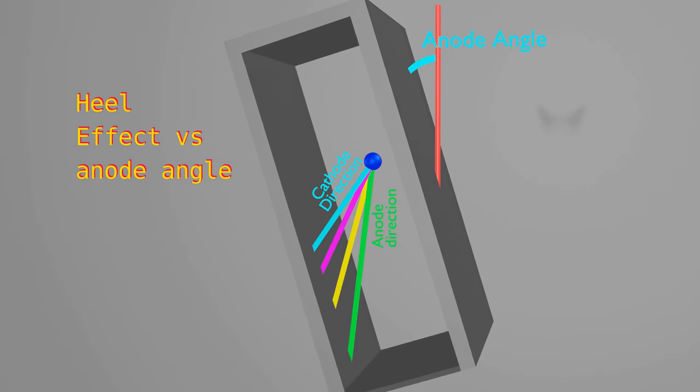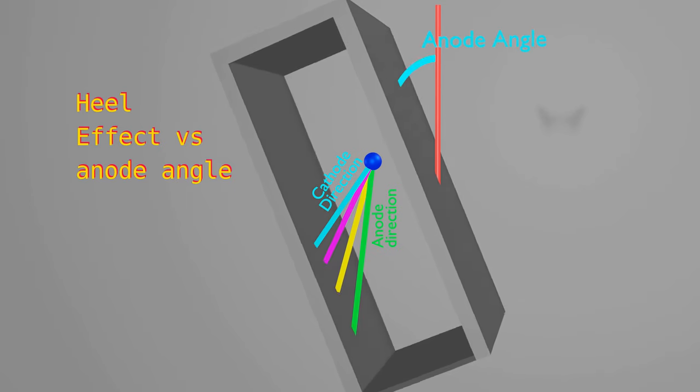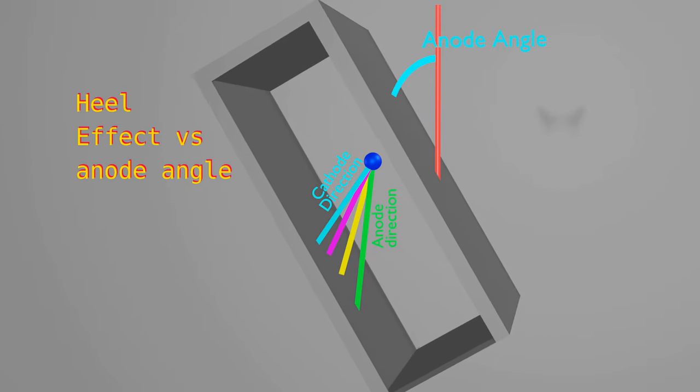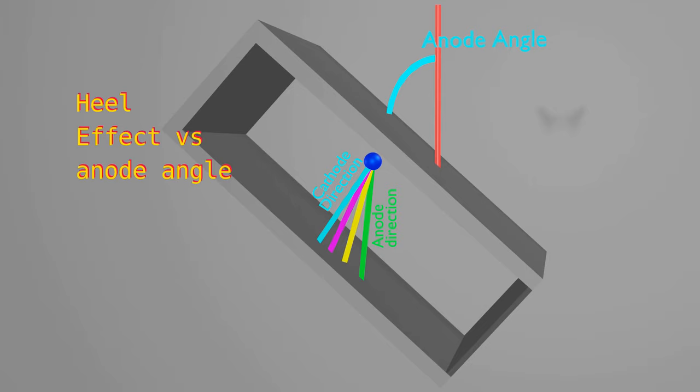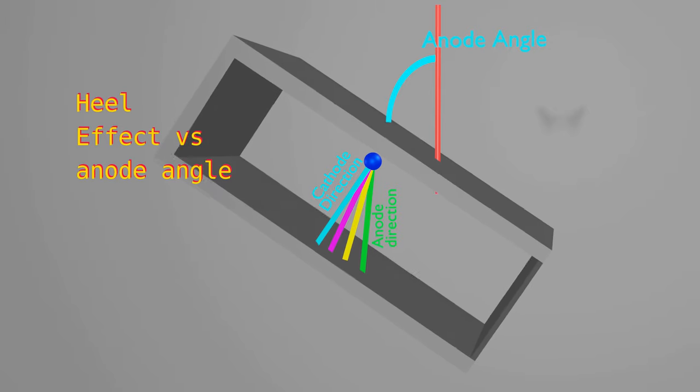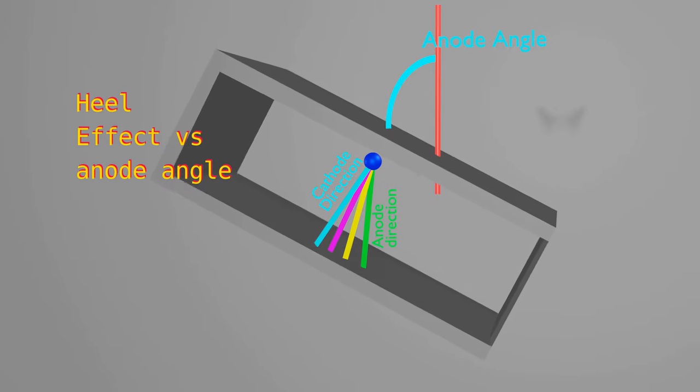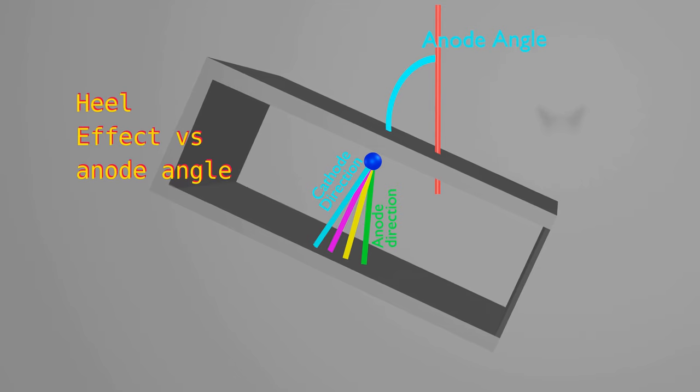Now we change anode angle. You can observe, as anode angle increases, the difference of path length along anode side and cathode side decreases. So, the difference in absorption or intensity variation will reduce with anode angle. We can say, with increasing anode angle, heel effect reduces.